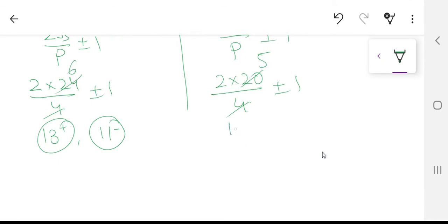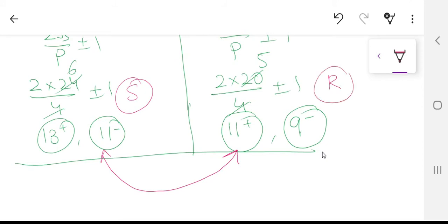So 10 plus 1, this is 11. So this will be the positive moving harmonic. And 10 minus 1, 9. So this will be negative. So now what has happened? In this type of arrangement, I have the 11th harmonic from the stator and the 11th harmonic from the rotor. This is the stator side, this is the rotor side. So what is now going to happen? There is again going to be a locking phenomenon between the stator and the rotor because of the 11th harmonic.